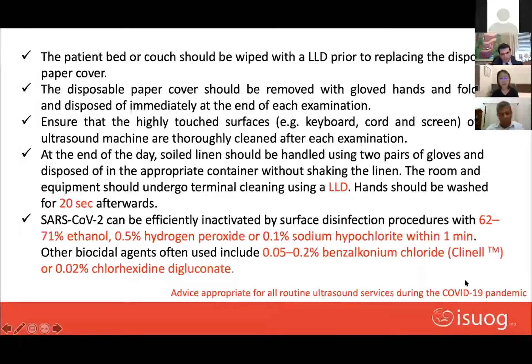And here I'll give you some examples of what we call low-level disinfectant, and the steps you need to take for cleaning and disinfecting the probe after its use in a COVID-19 case. When you clean, you need to disconnect the transducer, remove the transducer cover, if applicable, and dispose of it in clinical waste. You need to rinse the operative end of the transducer with running tap water, clean the transducer with a soft brush and non-abrasive detergent, rinse the transducer with tap water, clean the transducer cable with a low-level disinfectant wipe, and then dry with a cloth or towel.